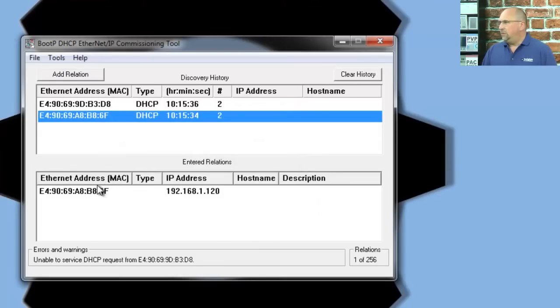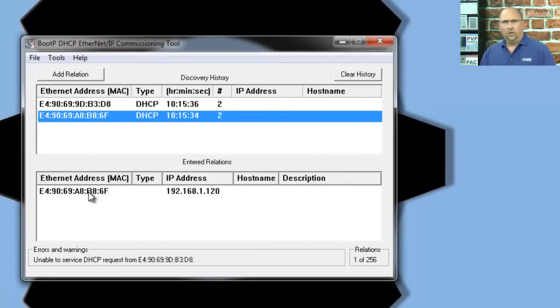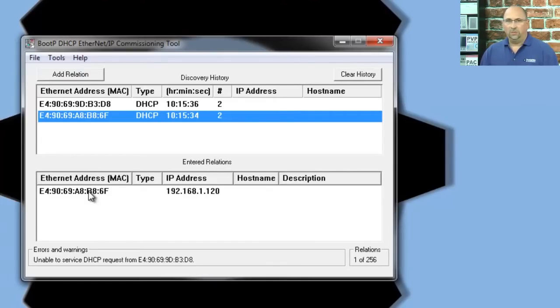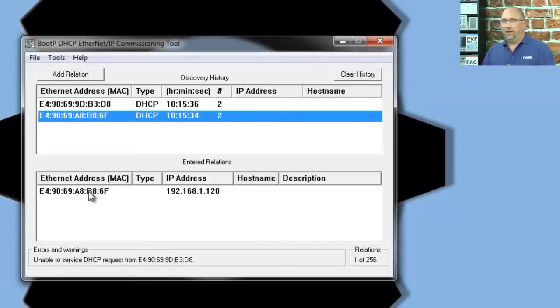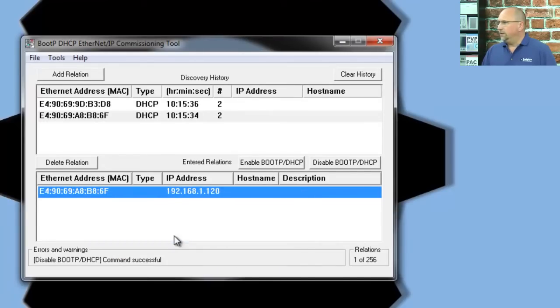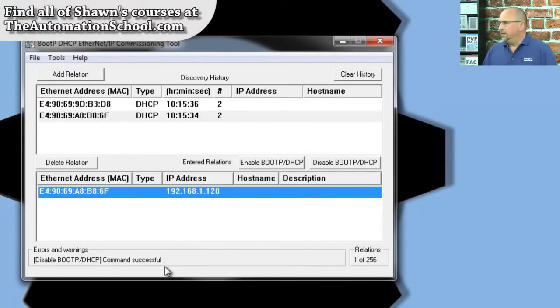Now, with some Allen-Bradley devices, you can actually disable BOOTP here. And you need to disable BOOTP because if you don't, next time you cycle power to the unit, it's going to ask for a new address again. So, that's important. Let's try it with this. I don't believe the 820 does, but let's try it. Disable BOOTP. Okay, and it said Command Successful.